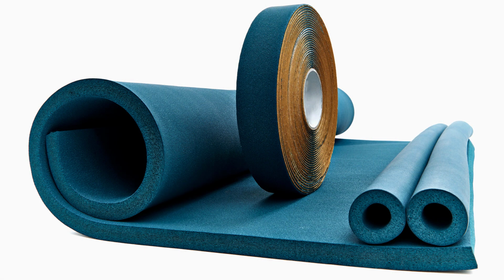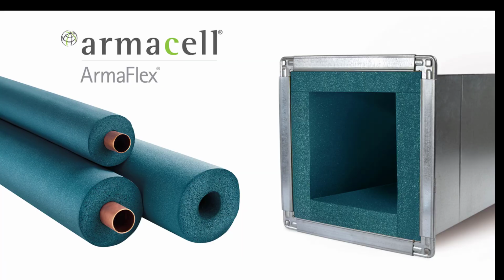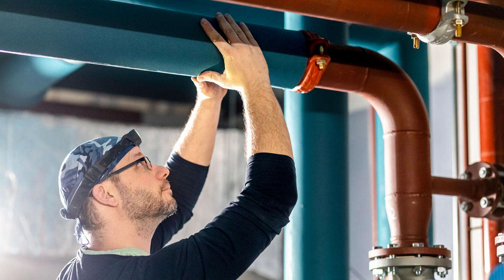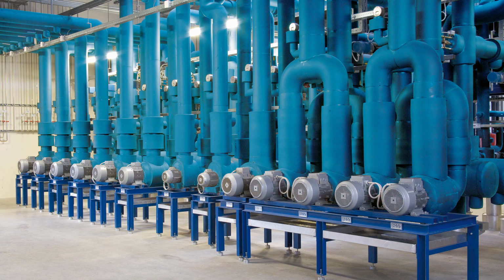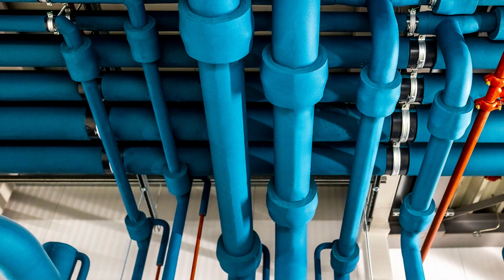In fact, ArmaFlex Ultima, our newest flexible elastomeric foam product, boasts an ultra-low water vapor permeability of 0.02 perm-in, delivering exceptional protection against condensation. As closed-cell materials, both the ArmaFlex and ArmaLight families offer this low water vapor permeability throughout the material. So even if surface damage were to occur, all those cells below the surface would still have this low water vapor permeability, unlike other materials that rely on jacketing or other vapor barriers for this protection.